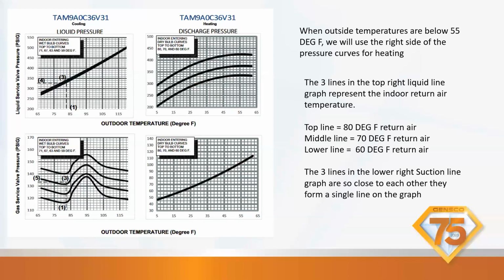And when you're on site too, you can call in and we can go over this, review it too, just in case you want to make sure you're perfect. The three lines at the top right liquid line graph represent the indoor return temperature. Okay, so this is your liquid side. Here's our pressures. Here's our outdoor temperature listed at the bottom. Then top line is 80-degree dry bulb inside. This represents an 80-degree return air. Our middle line is 70-degree return air. Lower line is 60-degree return air. And it stipulates that right here.